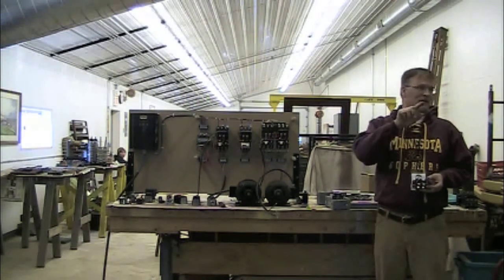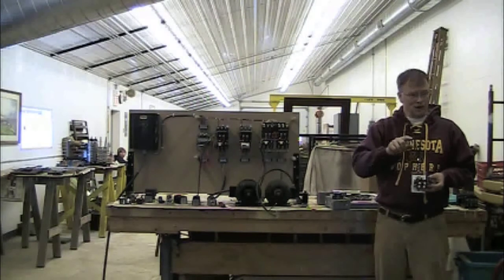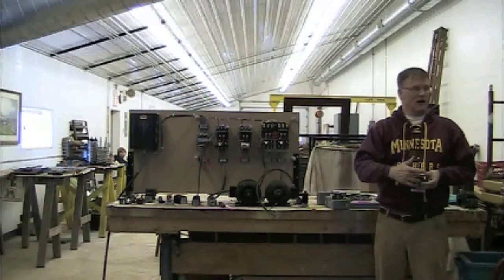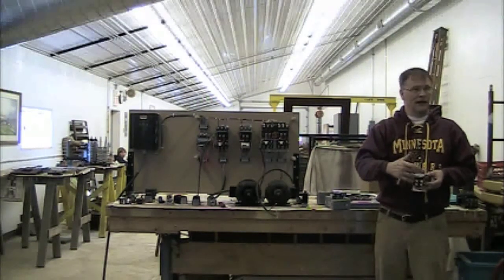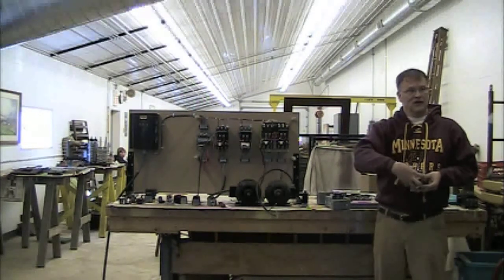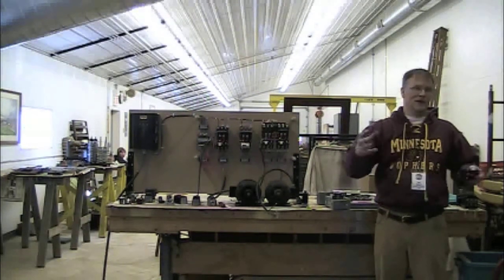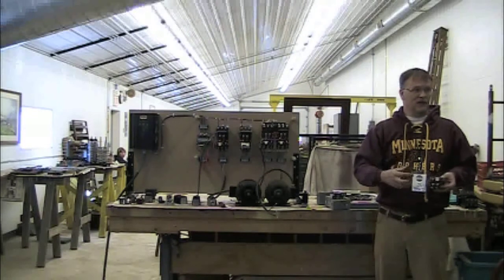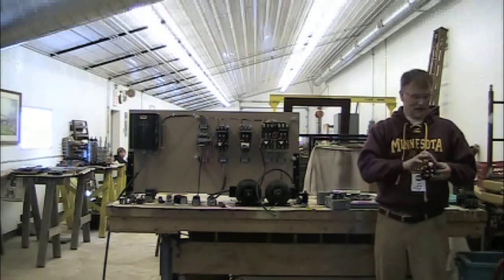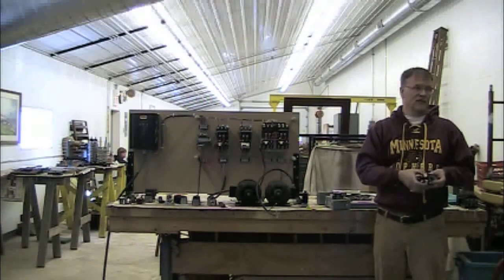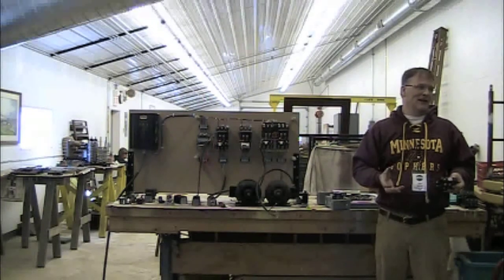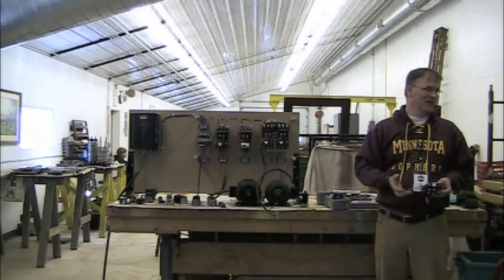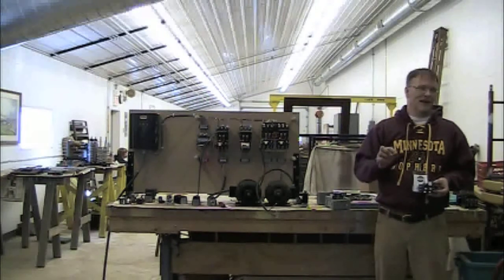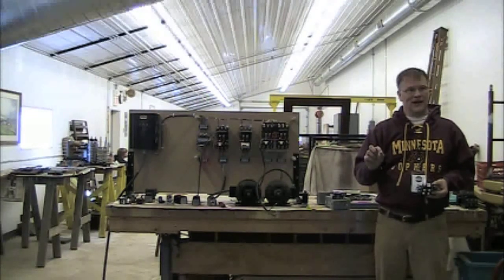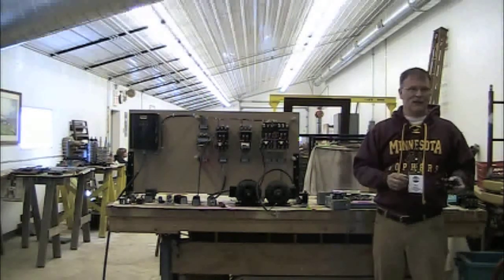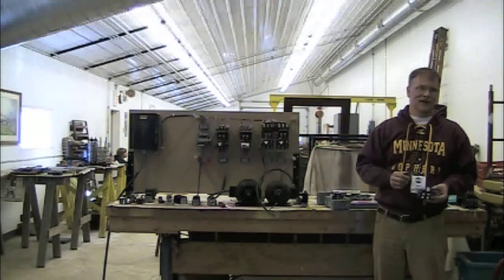But by doing that, they're running the same current on the motor leg through both of these starter positions that's controlling one leg, and also through the other. So the heating value that was determined for those charts is still fulfilled because you're heating all these positions. If one of them is just sitting there cold, then it's not going to heat at the same rate, and the value doesn't make sense. Other starter manufacturers actually just give a current rating on them. Allen Bradley's kind of weird in the way that they do it.